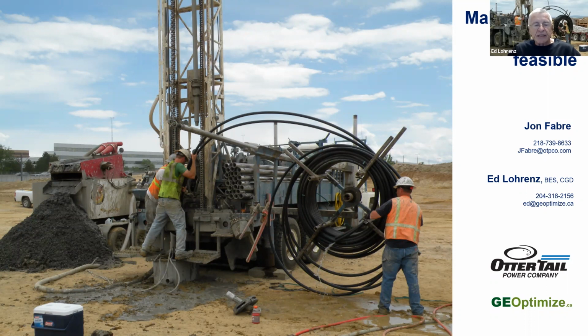It's not going to be exact. It's going to be probably 15, 20, 25% off of where we end up, but it's going to be a lot more accurate than rules of thumb would maybe suggest. At least you've looked at what the geology is and got a reasonably good estimate of that type of building in that climate.